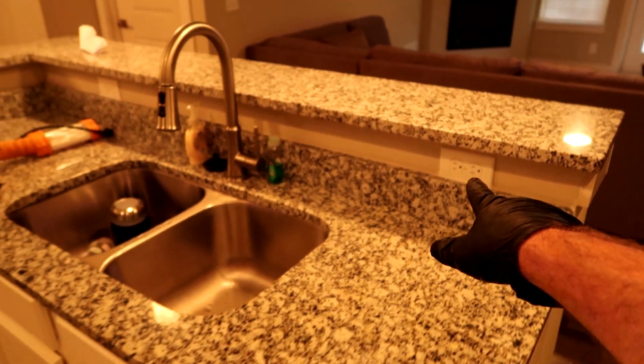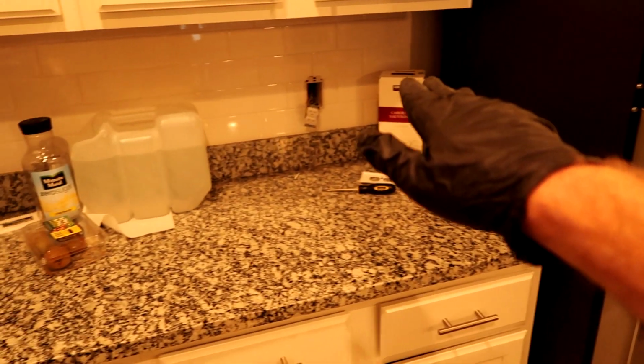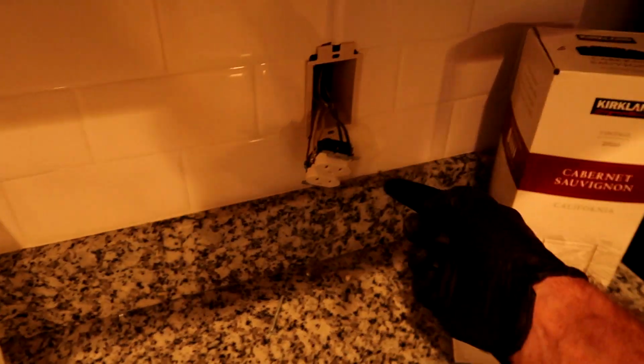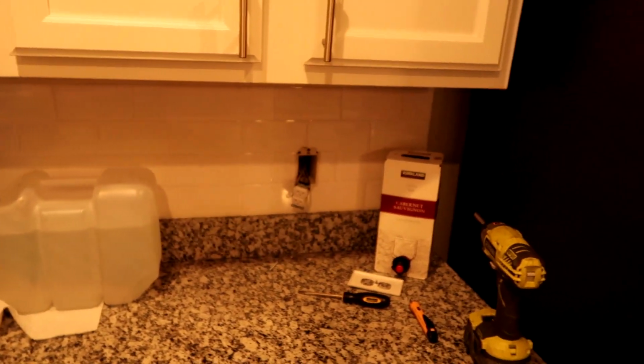Alright, Skid, that was it. Hope this helped some of you guys out. If your wires are hot, your outlets are hot, but nothing's coming on, you're just gonna have to start following the daisy chain. Find the loose neutral, the loose hot. Here, the neutral was on the wrong side, and the hots were a little loose, but that's it, man. I'm just gonna button it up and put the covers back on.